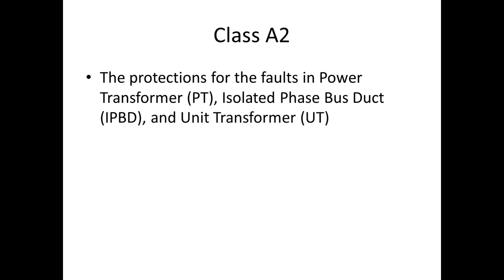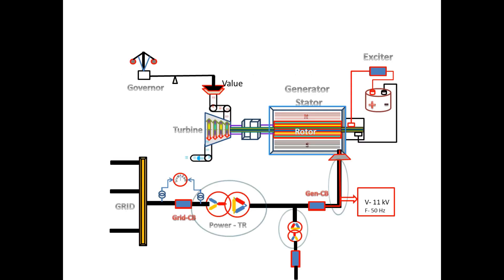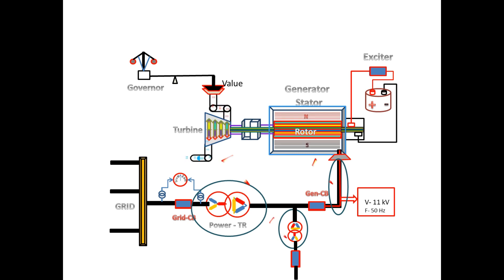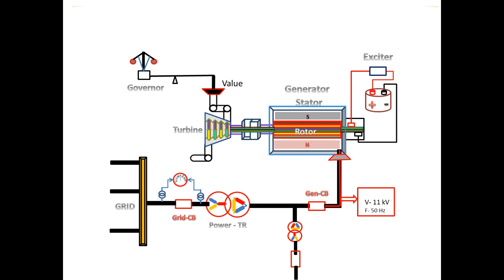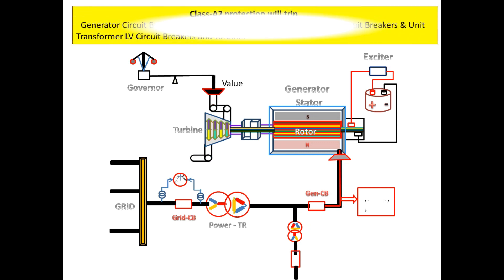The power transformer is also called generator transformer. If the fault occurs in the following components, the Class A2 will trip the following circuit breakers: generator circuit breaker, field circuit breaker, power transformer circuit breaker, and unit transformer LV circuit breaker and turbine.